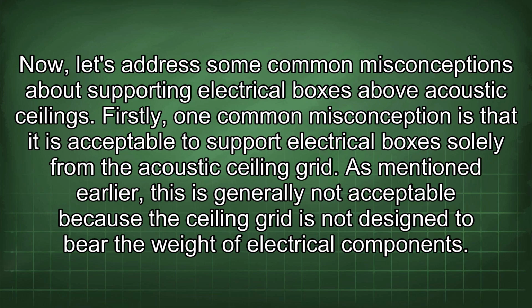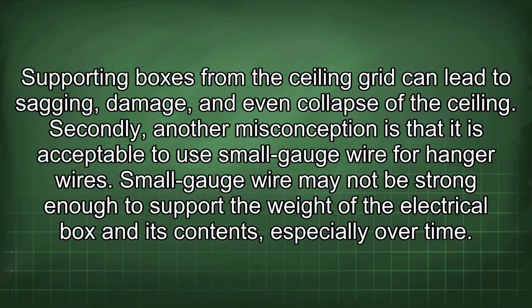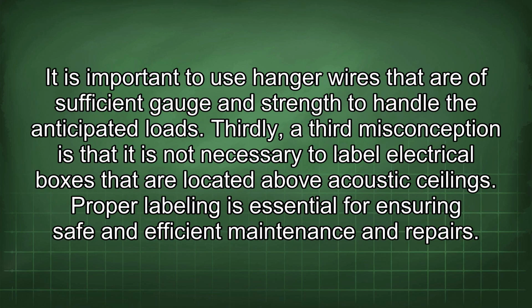As mentioned earlier, this is generally not acceptable because the ceiling grid is not designed to bear the weight of electrical components. Supporting boxes from the ceiling grid can lead to sagging, damage, and even collapse of the ceiling. Secondly, another misconception is that it is acceptable to use small gauge wire for hanger wires. Small gauge wire may not be strong enough to support the weight of the electrical box and its contents, especially over time.